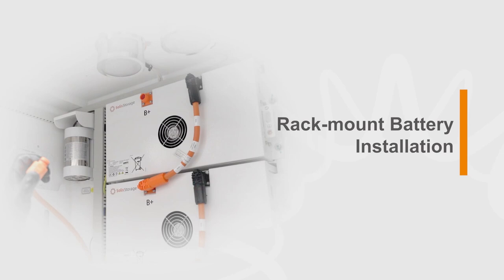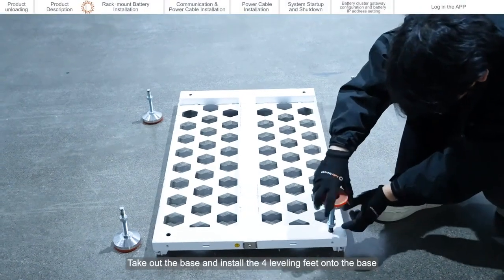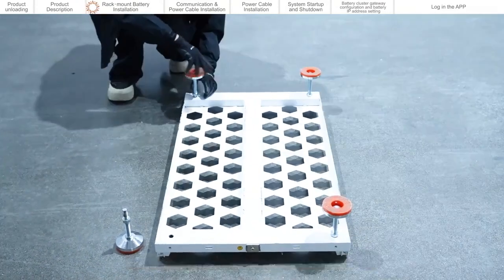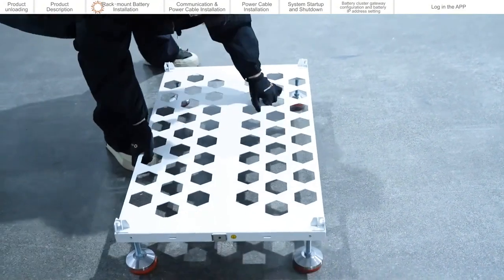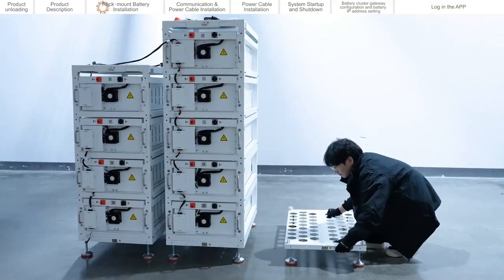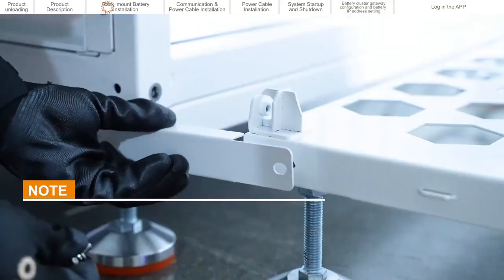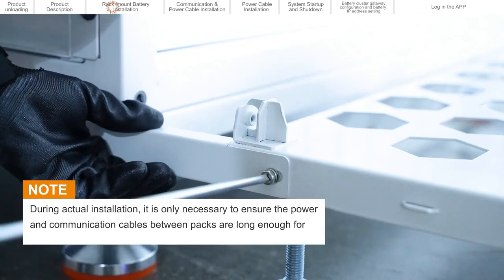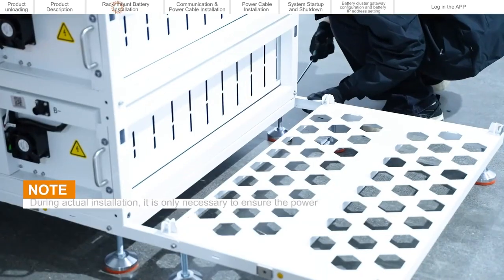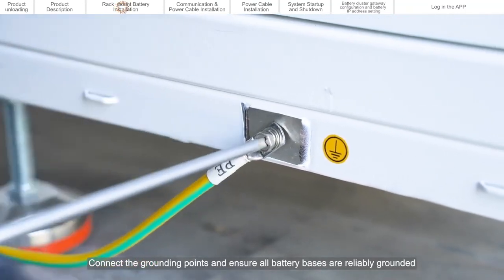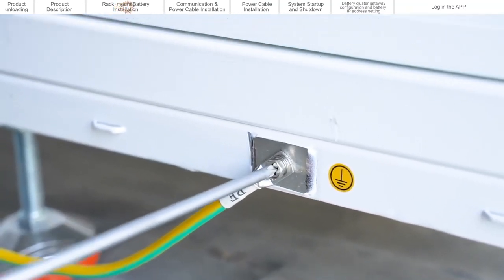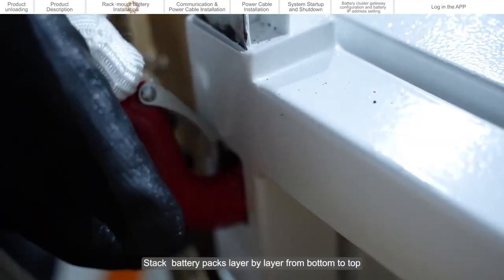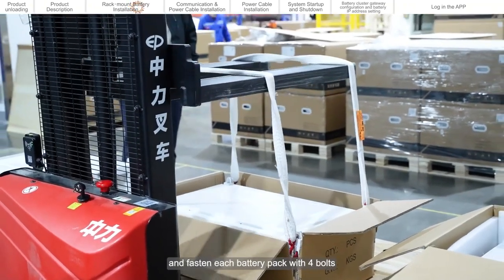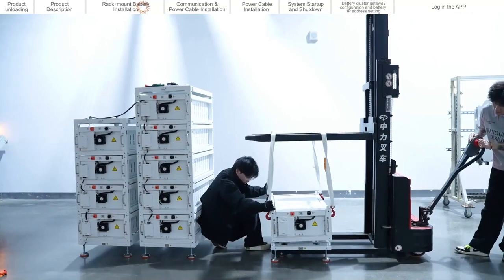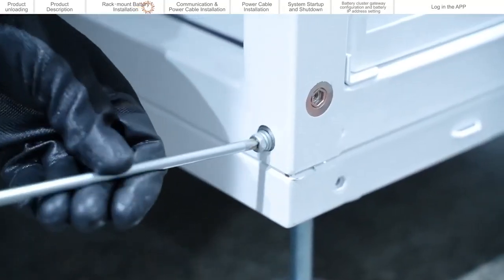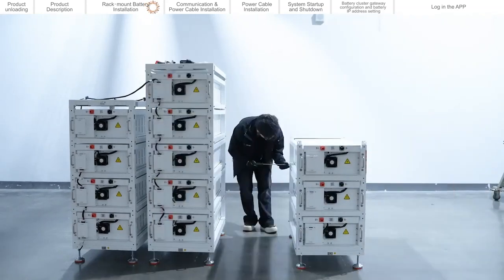Rack mount battery installation. Take out the base and install the 4 leveling feet onto the base. Connect adjacent bases with limit parts. Connect the grounding points and ensure all battery bases are reliably grounded. Stack battery packs layer by layer from bottom to top, and fasten each battery pack with 4 bolts. Fasten each battery pack with 4 bolts.